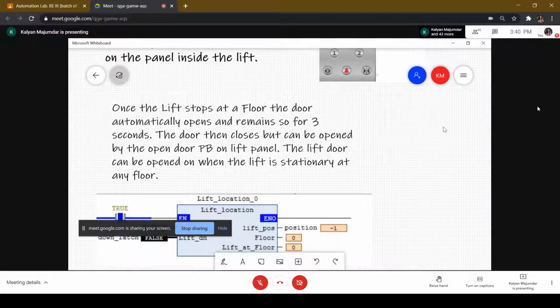Whenever it stops at a particular floor, the door opens automatically and remains open for a certain amount of time, implemented using a timer. After that it automatically closes. But if that time wasn't sufficient, you can press the open door button, which extends the door open duration for a certain amount of time, then closes. You can press it again and it extends again, and this process continues. The interlock is that the door can only be opened when the lift is stationary at a particular floor.